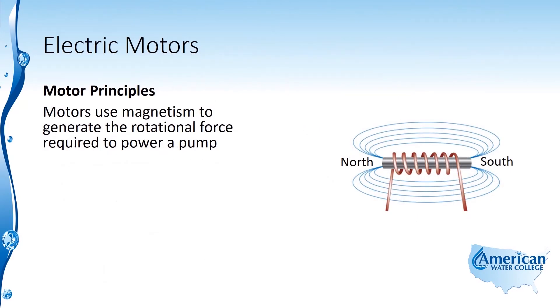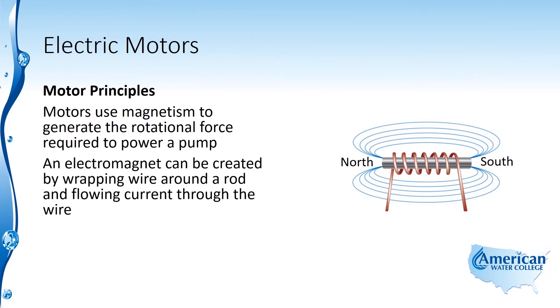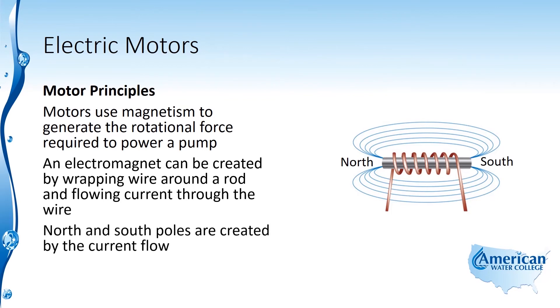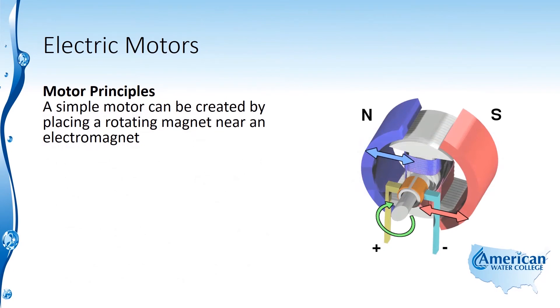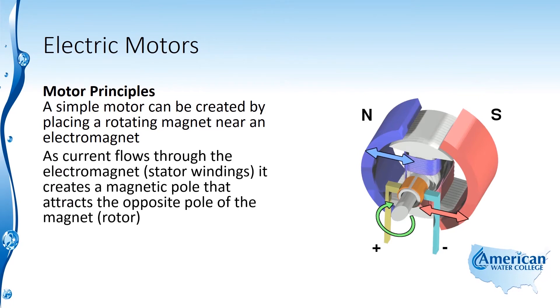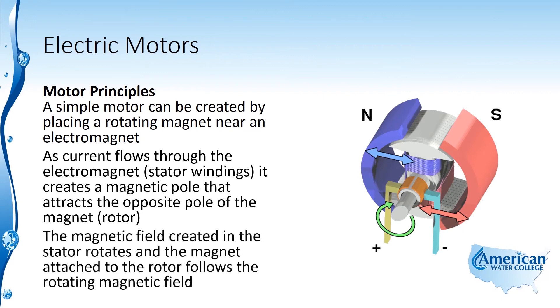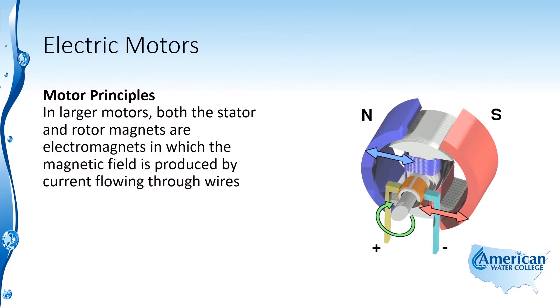Motors use magnetism to generate the rotational force required to power a pump. An electromagnet can be created by wrapping wire around a rod and flowing current through the wire. North and south poles are created by the current flow, and as the current direction changes, so does the polarity of the magnet. A simple motor can be created by placing a rotating magnet near an electromagnet. As current flows through the electromagnet — representing the stator windings — it creates a magnetic pole that attracts the opposite pole of the magnet, or the rotor. The magnetic field created in the stator rotates, and the magnet attached to the rotor follows it. In larger motors, both the stator and rotor magnets are electromagnets, with the magnetic field produced by current flowing through the wire.